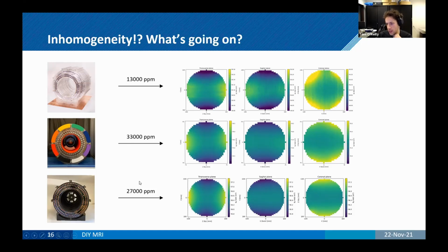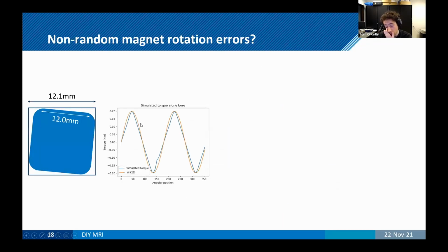So that was frustrating, especially because these inhomogeneities are really difficult to deal with, even after shimming. You want to be much closer to this than to this. What we came up with as an explanation was basically that when you cut the holes to put the magnets inside, that hole has to be a little bit bigger than the magnet that you're pushing inside, just because of friction and things like that. So that magnet can, once it's in location, rotate a little bit. It's an in-plane rotation. And if you simulate that as a random rotation, you get a little bit worse homogeneity, but you don't get these distinct patterns.